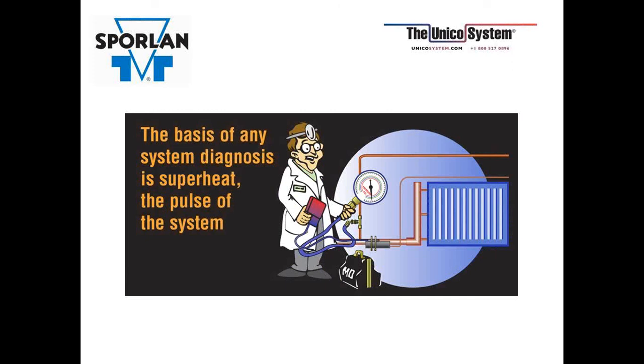And like I said, if you call tech support, they're going to ask you what your superheat is. So be prepared. Don't tell us what we want to hear. Tell us what the actual superheat is. One of my people that's on the line right here says, I've never seen a gauge that says "fine" on it. They do have numbers on them.